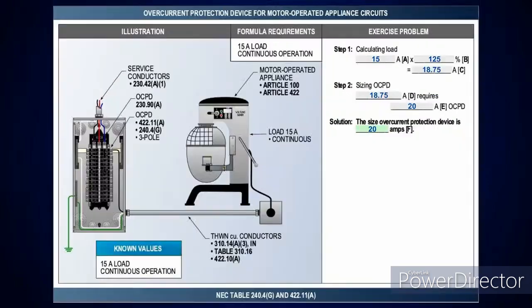Nice. And then we did a basic branch circuit on the third day. I said if you have a continuous load, and you look at Article 100, that means it could operate for 3 hours or more, you take it at 125%. So I'd take 15 amps times 125%, which gives me 18.75 amps. Then you just use it like a small conductor, and you could look over at 240.4(D), but the next size for that would be a 20 amp with a number 12 wire.